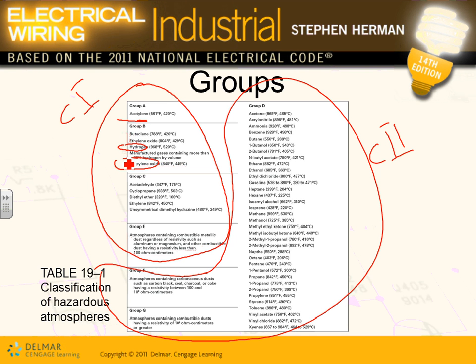So when you install a system in a hazardous location, a Class 1 location, you need to ask first, is it Class 1 Div 1? Yeah. What type of group material? Is it A, B, C, or D for gases, and then E, F, or G for dust? Any comments, guys? Any questions about the groups?